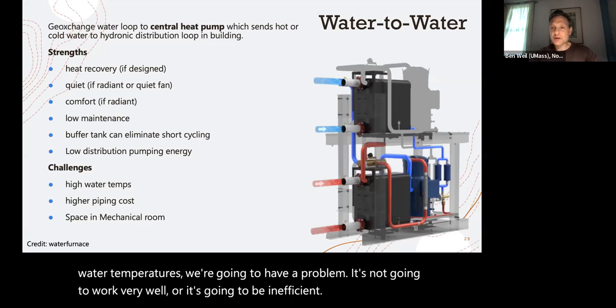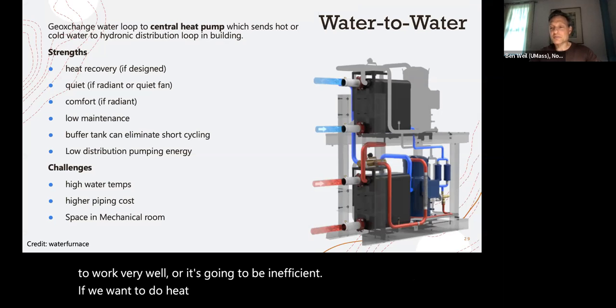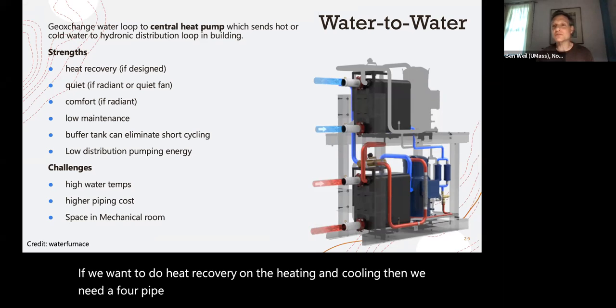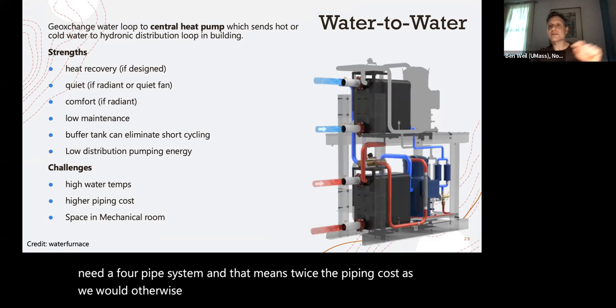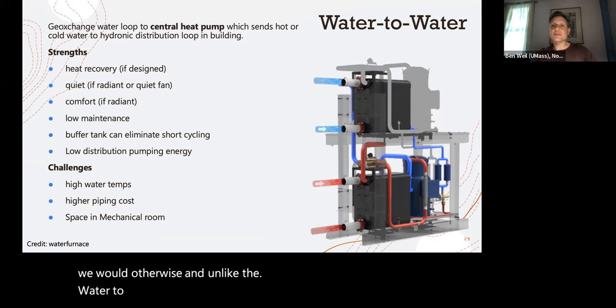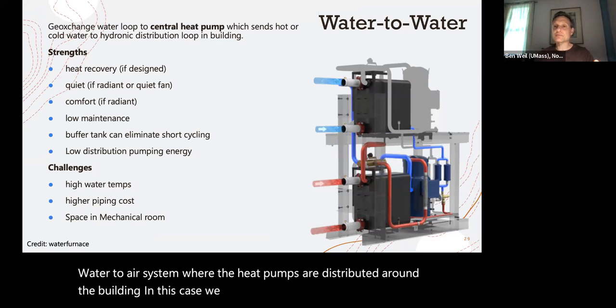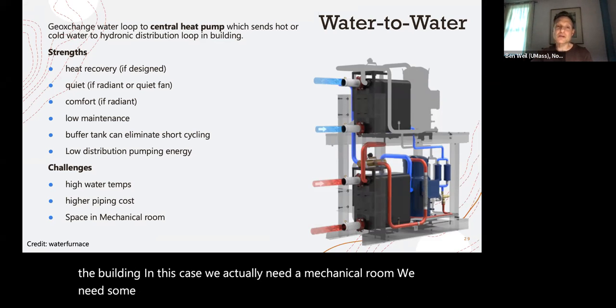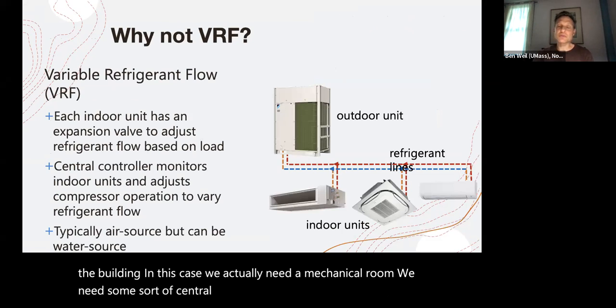If we want to do heat recovery on the heating and cooling, then we need a 4-pipe system, and that means twice the piping cost as we would otherwise. And unlike the water to air system, where the heat pumps are distributed around the building, in this case we actually need a mechanical room, some sort of central space. So it depends on what you're trying to do.